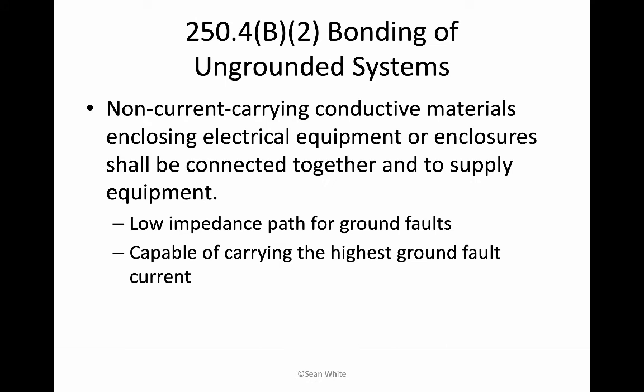250.4(B)(2), bonding of ungrounded systems. Non-current carrying conductive materials enclosing electrical equipment or enclosures shall be connected together and to supply equipment. So bonding is connecting everything together. It gives us a low impedance, which is like resistance, pathway for ground faults. So when there's a ground fault, we want it to go through quick right there.